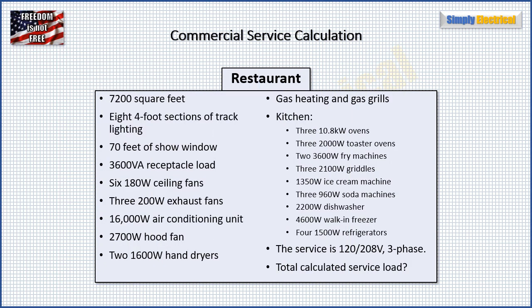Here is our example: a restaurant, 7,200 square foot building. We have eight four-foot sections of track lighting, 70 feet of show window, receptacles, ceiling fans, exhaust fans, an AC unit, a hood fan, some hand dryers, and the heating and grills are gas — which is important. Then we have our kitchen equipment all listed out, and lastly our service is 120/208-volt, three-phase. We want to find out what our total calculated service load is.